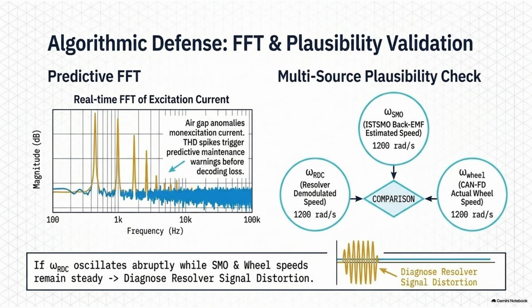Now, apply that to our motor. Remember that 0.05 millimeter wobble caused by the chewed-up bearing. Right, the physical eccentricity. Because that physical wobble constantly changes the magnetic resistance in the air gap, it actually modulates the electrical current. It adds a very specific low-frequency hum to the electrical symphony. The wobble creates a new instrument in the orchestra. Yes.